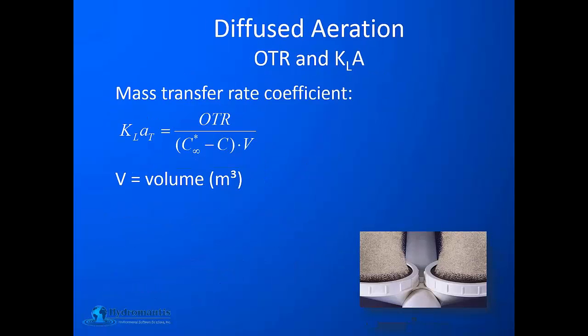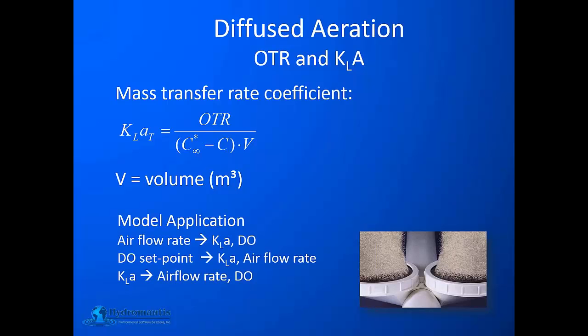Once we have determined the oxygen transfer rate, we use the standard equation for estimating KLA: oxygen transfer rate divided by the driving force, divided by the volume of the tank. The model can be applied in different ways: the user can specify air flow rate to estimate KLA and DO; start with a DO set point to estimate KLA and air flow rates; or enter direct KLA values to estimate air flow rate and DO concentration.